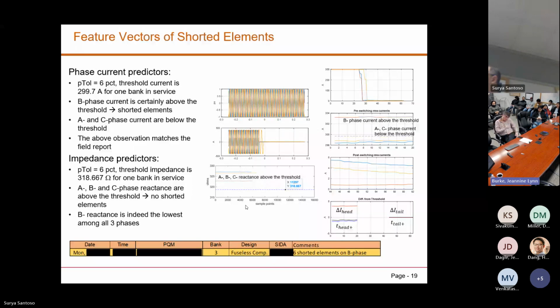What do you see in here? They are all above the threshold. So again, I have to compare it with the rated value of the impedance, taking into account some tolerance - the manufacturer's tolerance is 6% here. But you see that all of the impedances are above the threshold.